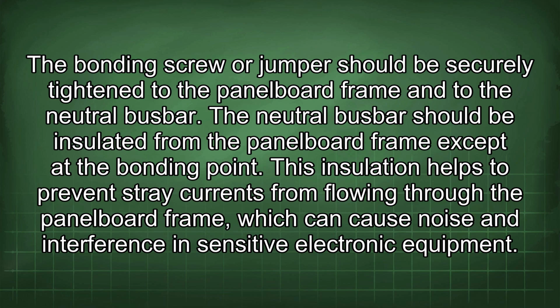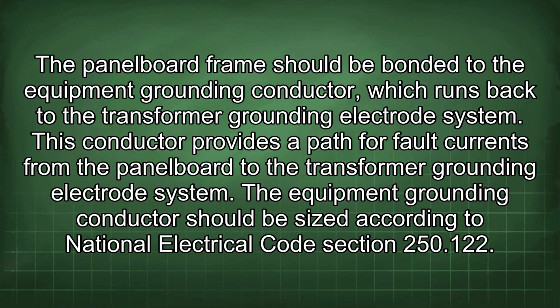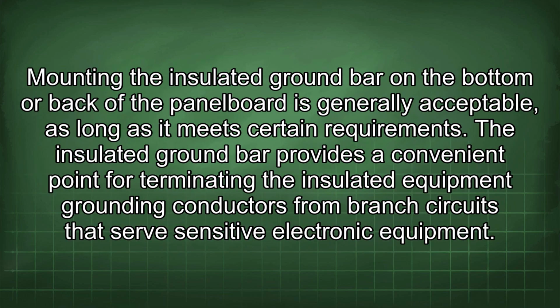The panel board frame should be bonded to the equipment grounding conductor, which runs back to the transformer grounding electrode system. This conductor provides a path for fault currents from the panel board to the transformer grounding electrode system. The equipment grounding conductor should be sized according to National Electrical Code Section 250.122. Mounting the insulated ground bar on the bottom or back of the panel board is generally acceptable as long as it meets certain requirements.